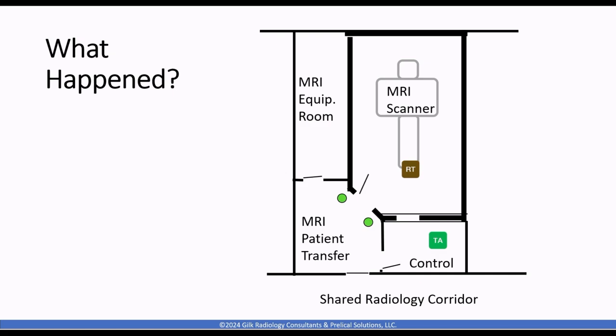This particular MRI scanner has what we call an undockable table. It detaches from the actual scanner. So you can load the patient on outside the room and roll that table in and essentially plug it into the scanner, and it operates just as one unified piece of equipment. So they know that the patient's coming down, they know they're gonna have to transfer this patient onto the MRI table. So the tech undocks it and essentially positions it so it's a straight shot through the door. So when the patient comes in on the regular hospital bed, they can just do a horizontal transfer onto the MRI bed. Once you pull it out of the room, slide it back in the room, scan the patient, no big deal.